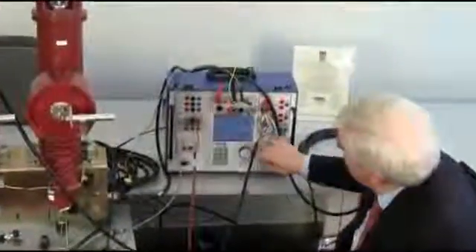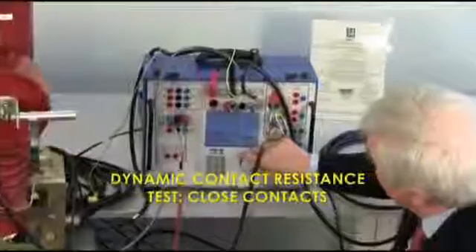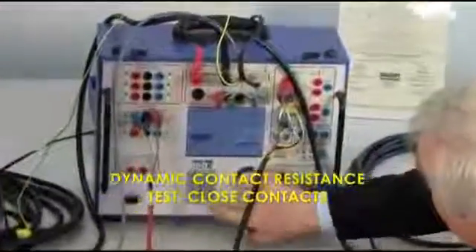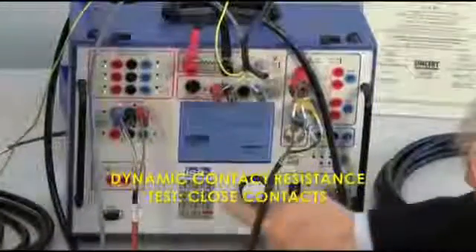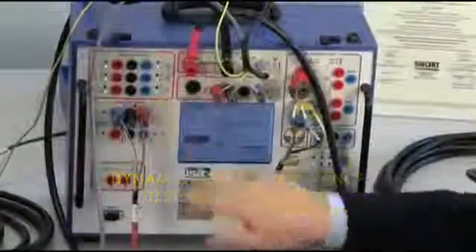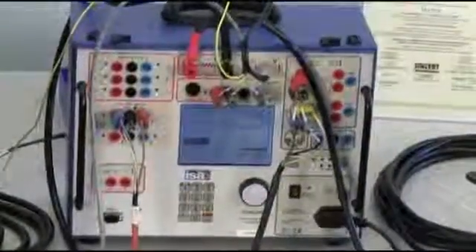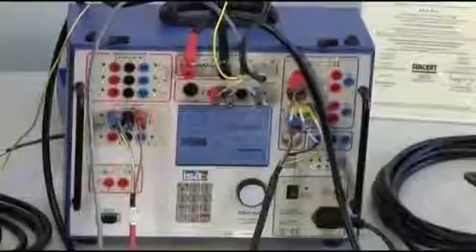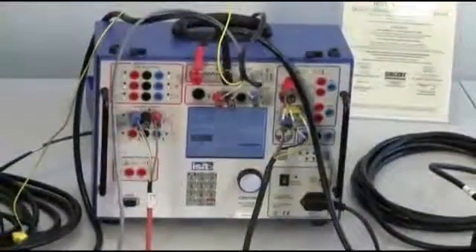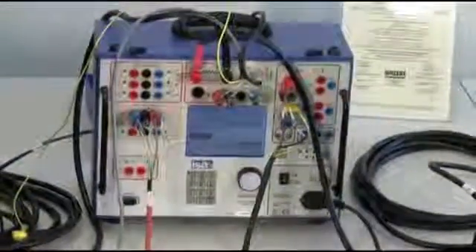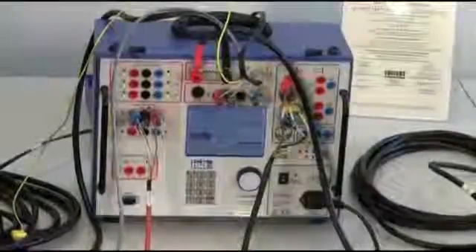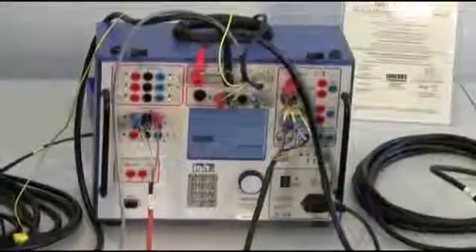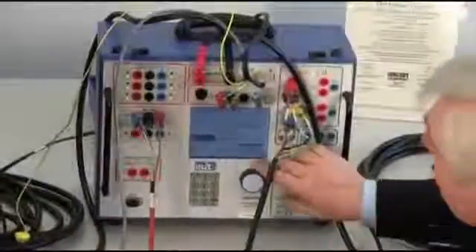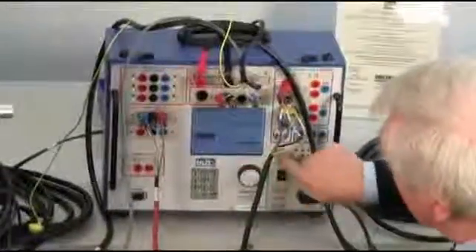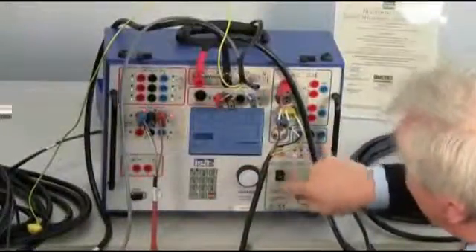For the close test, I also have to input here the nominal close that was about 60. But now this parameter is not critical because until the contact is open, of course, there is no current generation. So we will anyway record the current only when the contact starts closing. Then I press start, that's it.